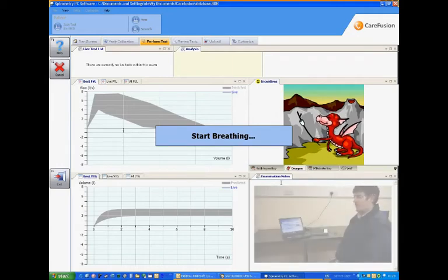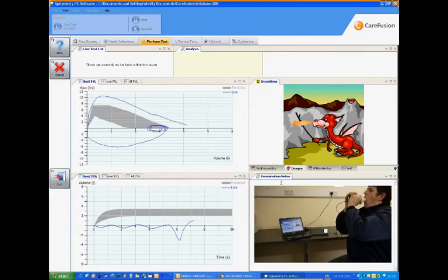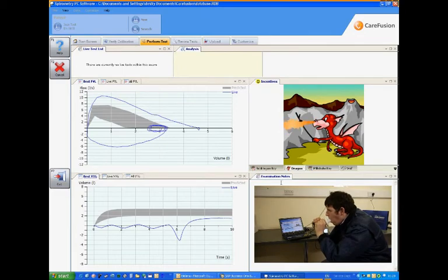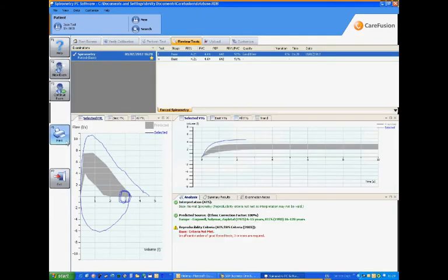The calibration can be done on the device and will be indicated on screen. If we now perform a test measurement — this is a full inspiratory and forced exhalation — you can see the measurement happening. Now you can see our measurements on screen. We can accept this and perform another measurement, but in this case we will press accept and done, and it will be saved as our records.